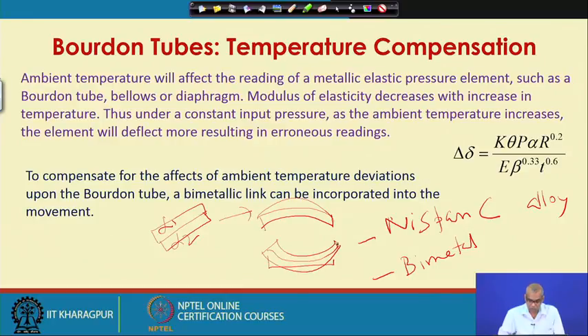Now, you can suitably design a bimetal strip and attach it to the Bourdon tube link. The idea is, the Bourdon tube's tip deflection will be more due to increase in temperature. Now, we have to suitably design a bimetallic strip whose deflection is the same for the change in temperature, but opposite.